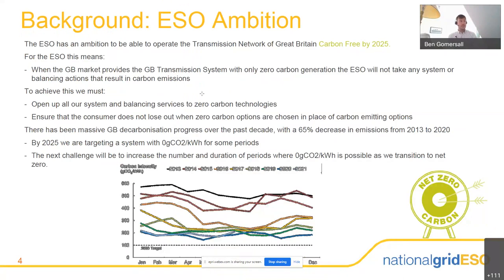So at National Grid ESO, we've got an ambition that by the year 2025, we want to be able to operate the system carbon free or net zero. What that means in practice is that if the system is going to dispatch itself in a position where there is zero carbon on the system, we as the operator don't want to be taking operability actions that resynchronize carbon emitting plant. And what that really means for inertia is that either there's enough inertia on the system that we can operate it, or the actions that we need to take in order to bring inertia back up to levels we want it at aren't going to be resynchronizing anything that's emitting carbon.